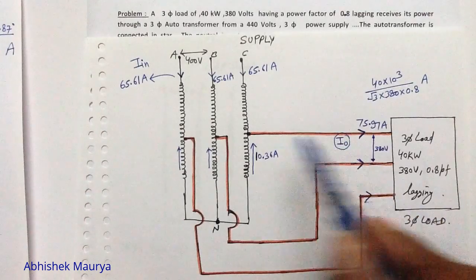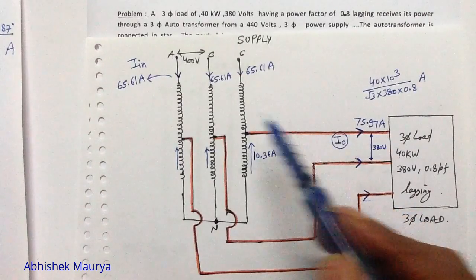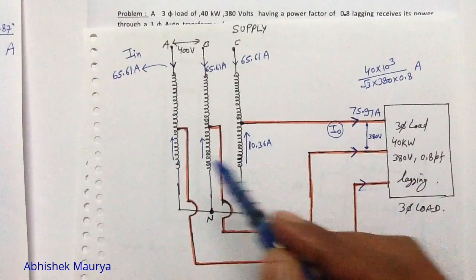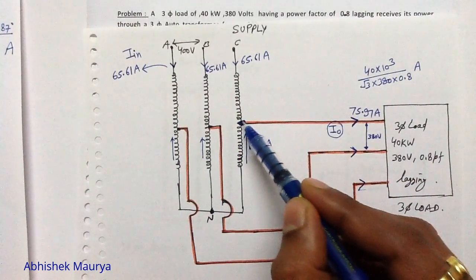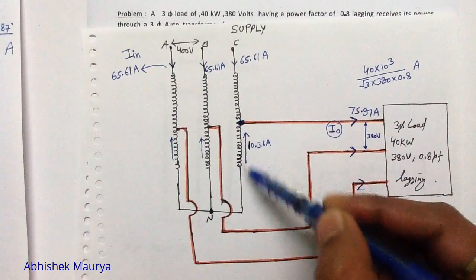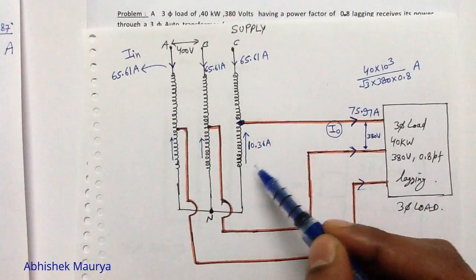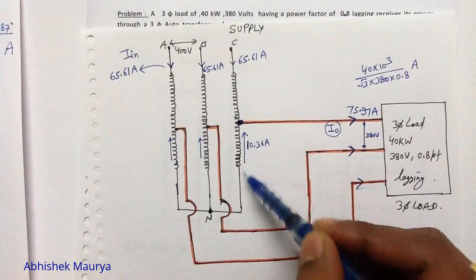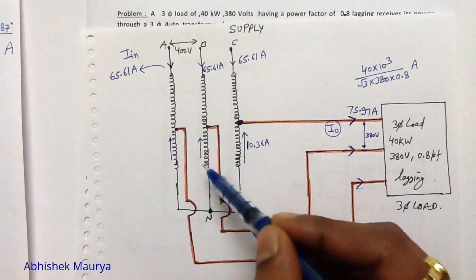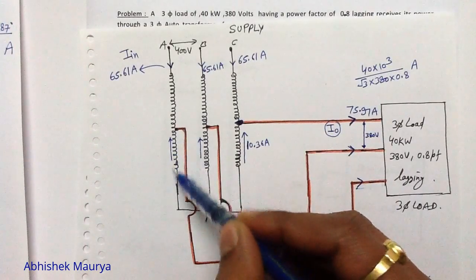Since both I0 and I_input are in the same phase, the angles are not needed when applying KCL. Applying KCL at the junction point, the current in the transformer winding is 75.97 − 65.61 = 10.36 amperes. This same 10.36 ampere current flows in all three windings. The input supply current of 65.61 amperes flows in the upper winding sections of all three phases.